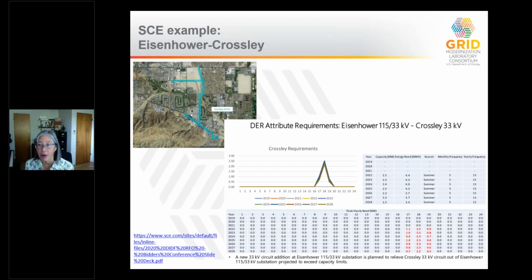So the blue is the Crossley circuit coming out of the Eisenhower substation. I realize it's hard to see, but the bottom right table shows in red that starting in 2022, they're going to start to be overloaded on that circuit. They're going to run out of capacity, and the hours of need are 5, 6, 7 o'clock, and they're going to need a maximum of 2.5 megawatts and 4.4 megawatt hours for that particular need. So this gives you an example of what this looks like.